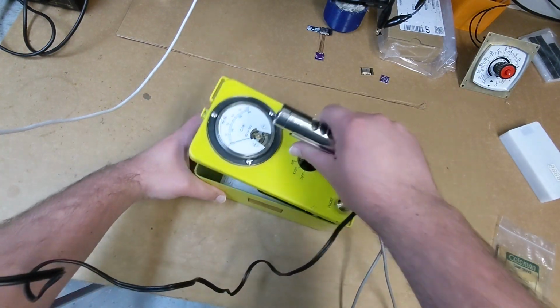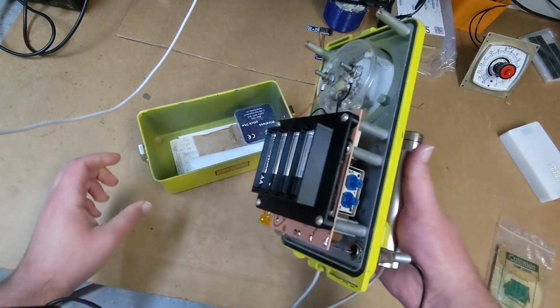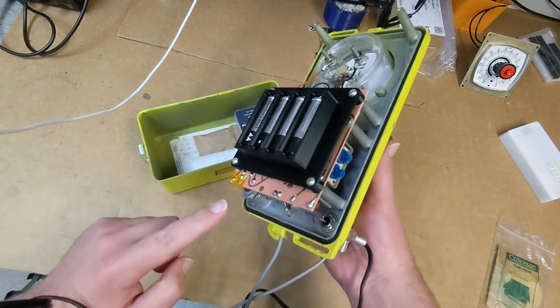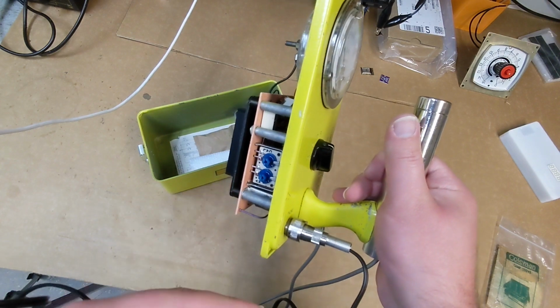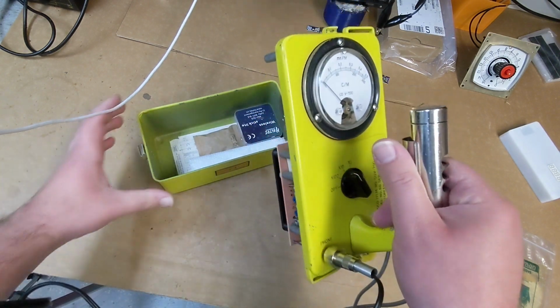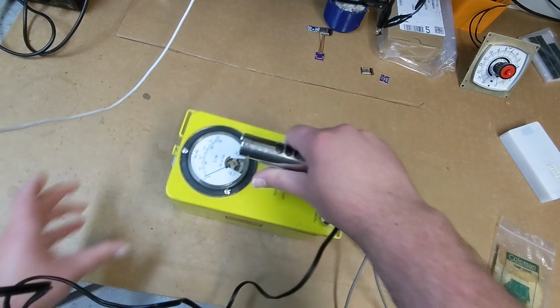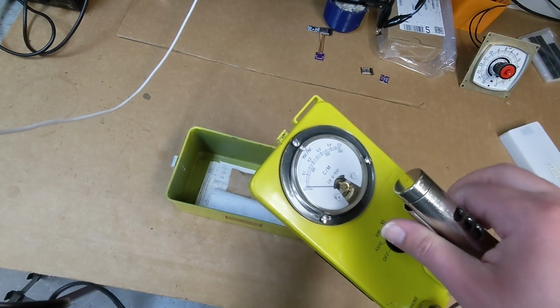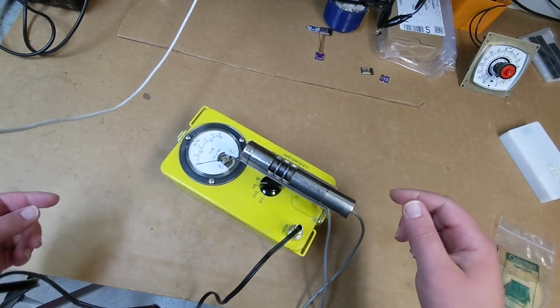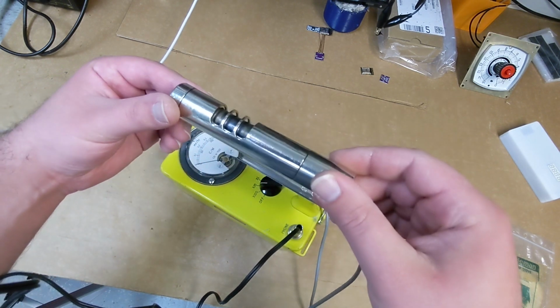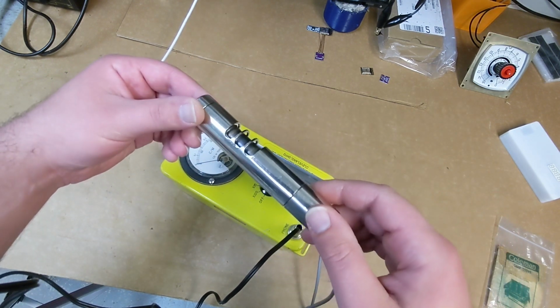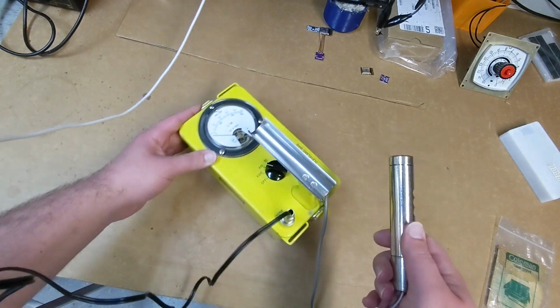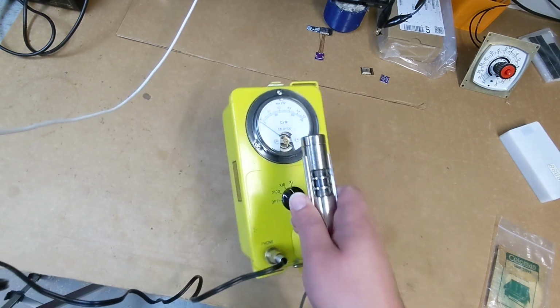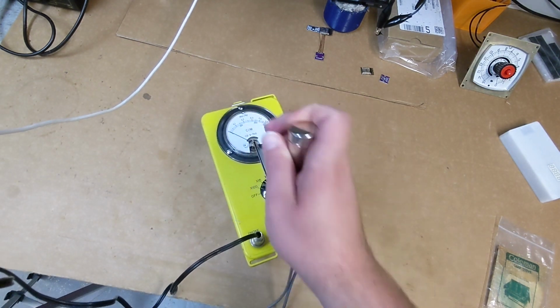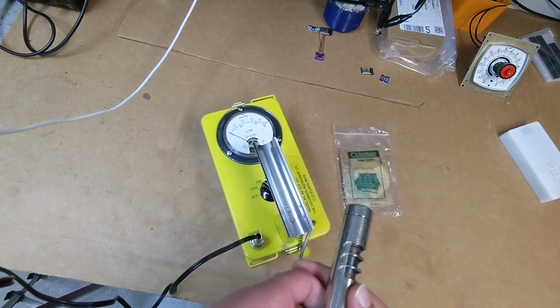So there you go. We've cleaned up the battery corrosion, made a new battery holder, cleaned up the main board, replaced some of the aging components with modern ones, and experienced 900 volts of shocking power. I was going to say we also replaced the tube with a new one that's not broken. And it's now working once again, just in time for the next Cuban Missile Crisis.